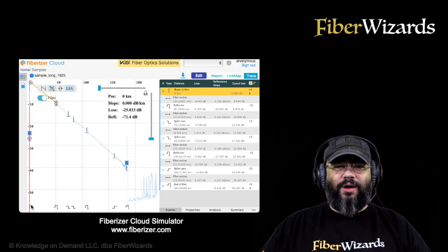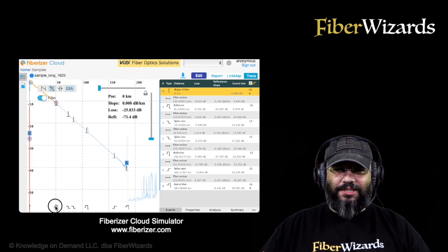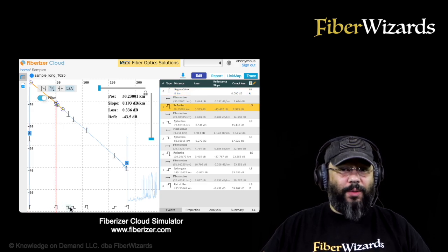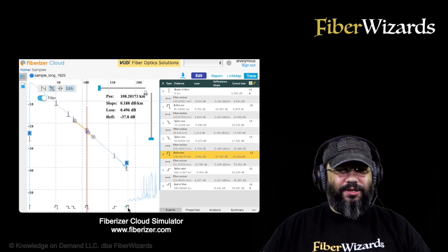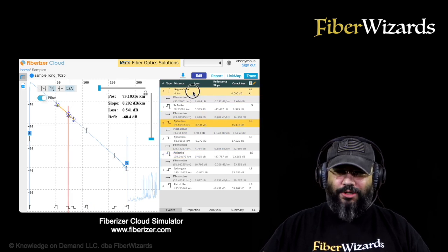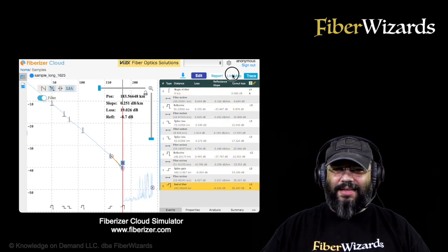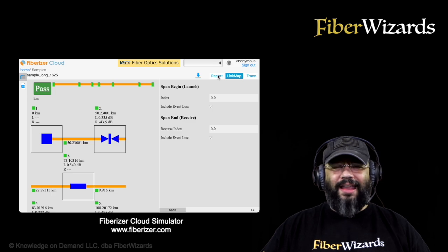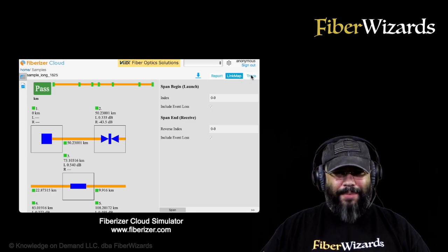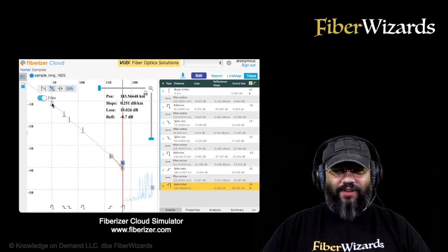Once the equipment processes the backscattering fluctuations, it creates graphical representations that tell you the distance of the span, the calculated total loss, and the resultant optical performance after the light travels through any connectors, splices, accessories, or any other performance impacting irregularities along the fiber path.